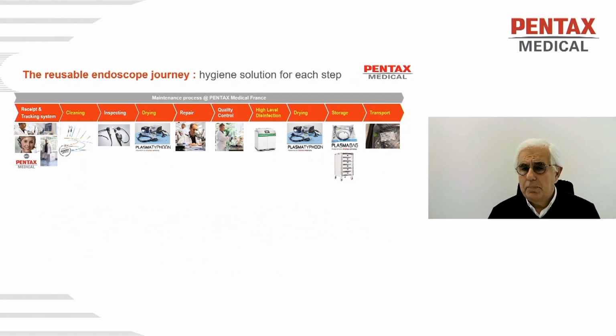Repairing is nothing extremely drastic, except that all the working space is clean. There is no contact between the previous and the following scopes, in order to make sure there is no potential cross-contamination. We have a high-level disinfection, and every endoscope that gets out of our disinfector is dried. It's dried in the Plasma Typhoon because it's fully automatic. It's reproducible, there's no human factor.